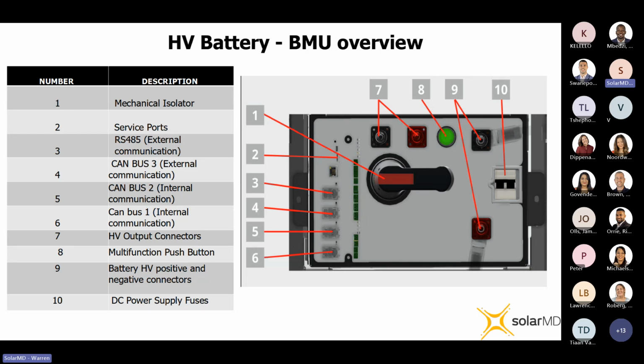Generally, it requires the manufacturer to come out to site with their team and fix things on site. Whereas with a design like ours, being modular, if there's a problem with the BMU, you can replace that, and it's relatively easily removed and replaced. If there's a problem with any one of the battery modules, the same applies - you can shut the system down, pull that battery module out and install a new one. If there's a problem with the BMS, it's even easier because it's a little circuit board, very easy to swap on site. So this modular design just means you're going to have an easier time getting the battery to site, commissioning it, physically installing it, and if there's a problem, it's a lot easier to resolve because you can just take out one of the components and replace it, versus dealing with forklifts and cranes and those sorts of logistical nightmares with immensely heavy things. So it's a lot more practical and easier to deploy as the EPC or as the installer.